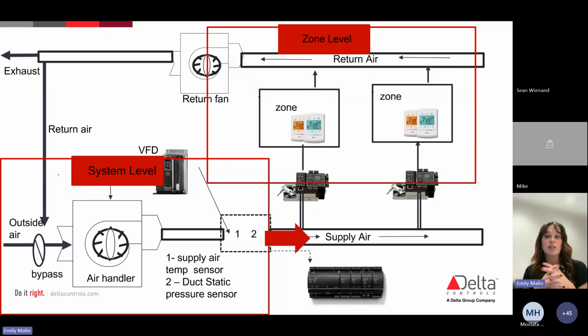So basically they're regulating the flow of CFM based on what the zone is calling for. And the way that this is actually done, you see in that little box in between where it says 1 and 2, we have a couple of different sensors. And Moose took us through what those sensors might look like as far as inputs and outputs. But in this scenario, we have one that's a duct static pressure switch. So if you're getting a lot of air flowing through there and you know that your zone is calling for even more air, as the pressure increases or decreases, we're always going to be monitoring that static duct pressure.